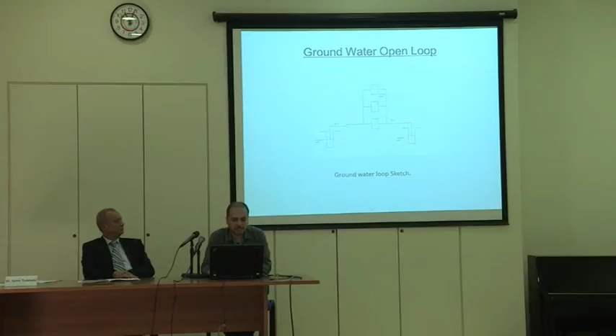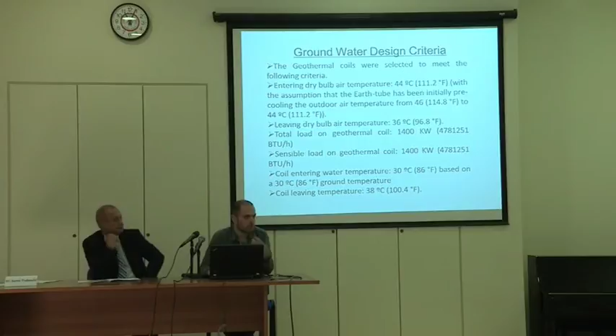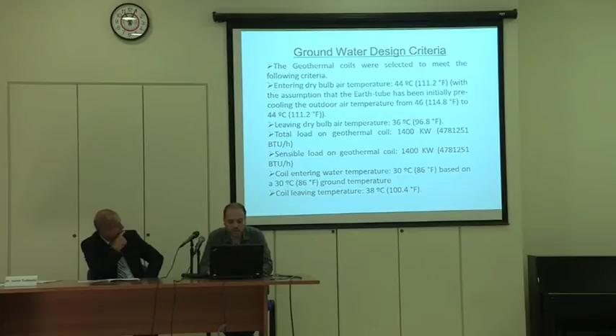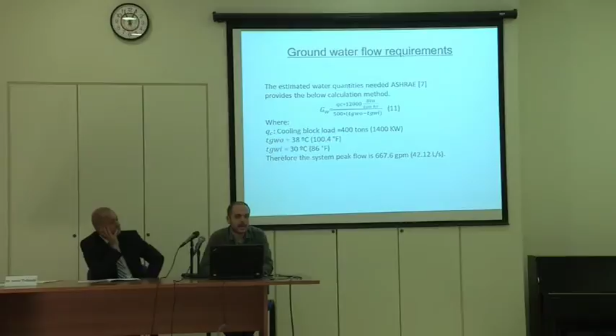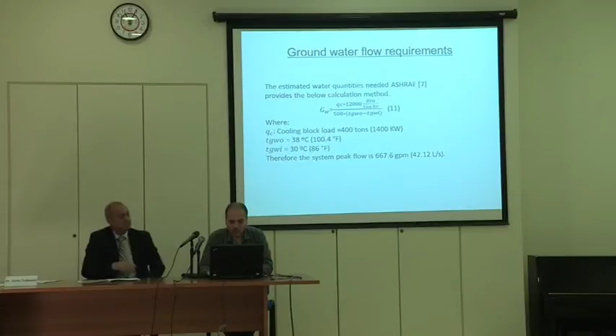We said, let's identify the quantity of water needed to dissipate that energy. Based on groundwater of 30 degrees and a water temperature difference of 8 degrees, we did not intend to increase that temperature much more than 38, just not to induce disturbance within the aquifer. We ended by requiring 42 liters per second of water. If we want to use the groundwater pumping, then we needed around 42 wells. If we want to go deep and reach the aquifer, then we can end up with 2 or 3 wells.